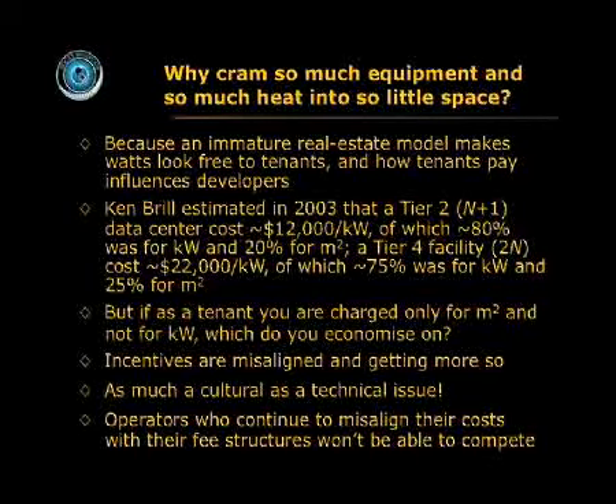But if we reward tenants for conserving square meters, not for conserving watts, then as operators we're stuck with a lot of extra costs that we're not charging for. This is crazy. It's completely misaligned incentives. And this is really as much a cultural as a technical issue, but fortunately the operators who misaligned their costs with their fee structures are starting to go out of business, and some of the smartest operators are now charging mainly by the watt, not by the square meter, or much less by the square meter, so that costs and fees get properly aligned, and this turns out to be very good for both parties. Then they don't try to get such impossible to cool power densities.